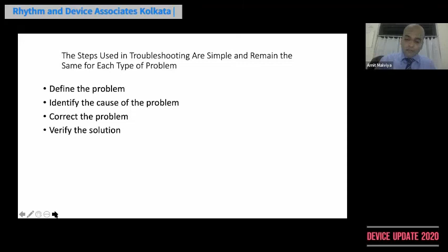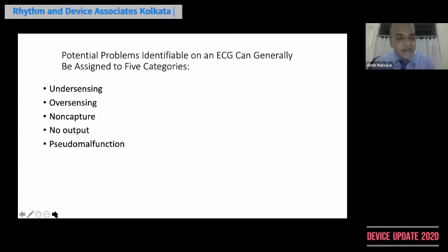It is either undersensing, oversensing, non-capture, no output, or pseudo malfunction of the pacemaker. Now these upper four, undersensing to no output, are real malfunctions of the pacemaker related to the mechanical failures of the pacemaker components. Whereas pseudo malfunction is mostly related to abnormalities in the intervals and the parameters set during pacemaker interrogation, which may lead to erroneous pacing by the pacemakers, resulting in pacemaker mediated tachycardia, etc.